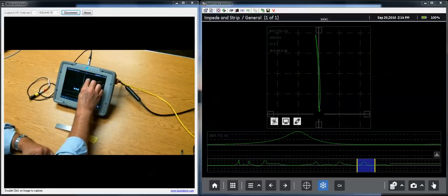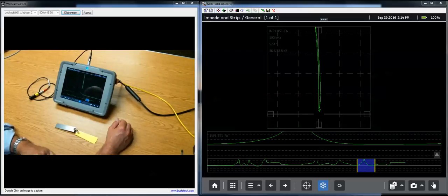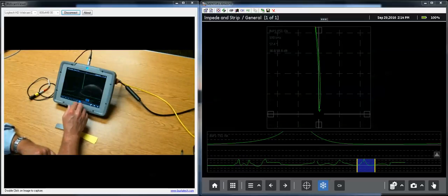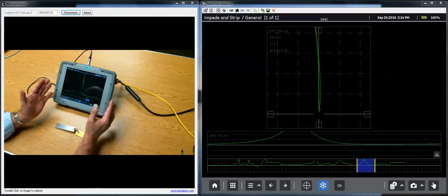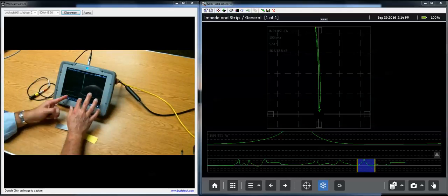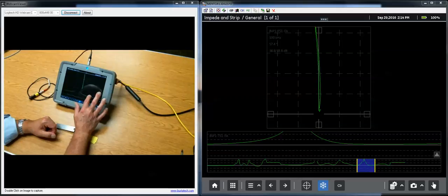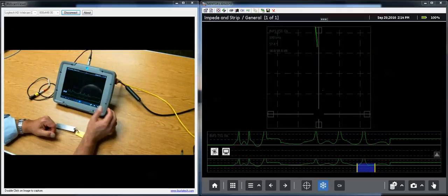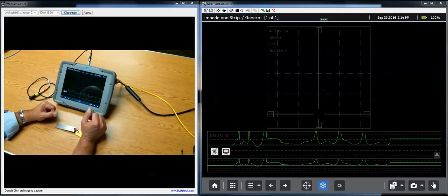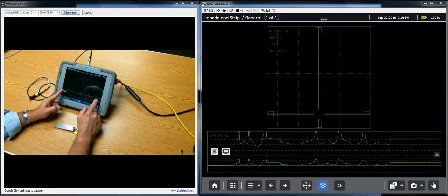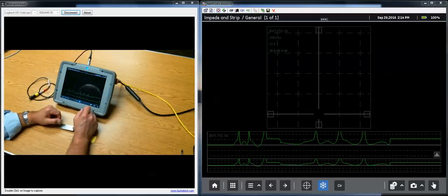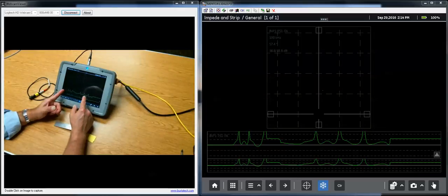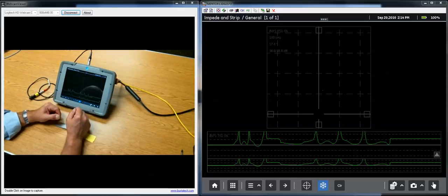Coming back to the strip chart, if I want to extend that back to all of the signal, all of the 10 seconds, if I tap twice in the main part of the view, it discards my cursors and now I see the entire area again. And one thing that sometimes you would want to do is see your entire buffer overlaid at one time on the Lissajous.